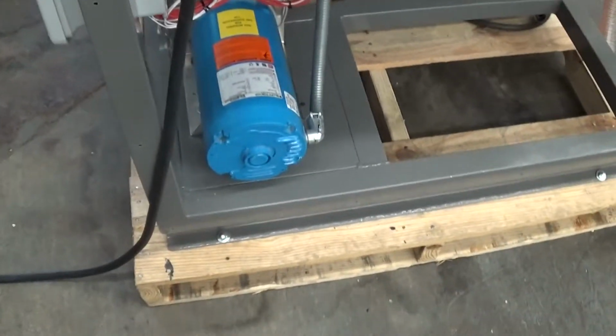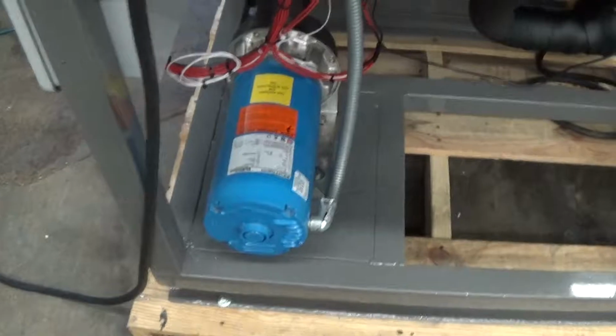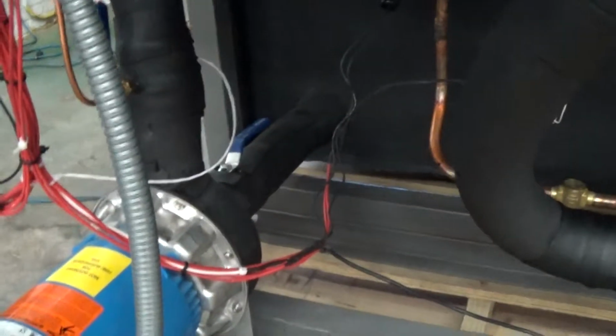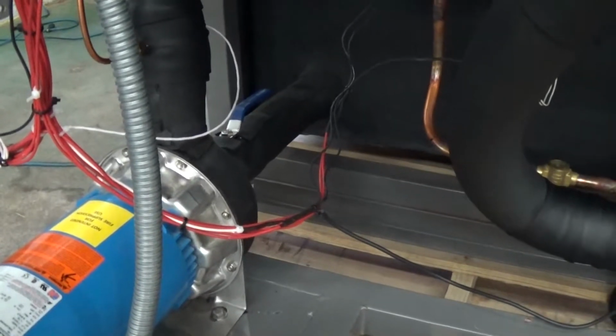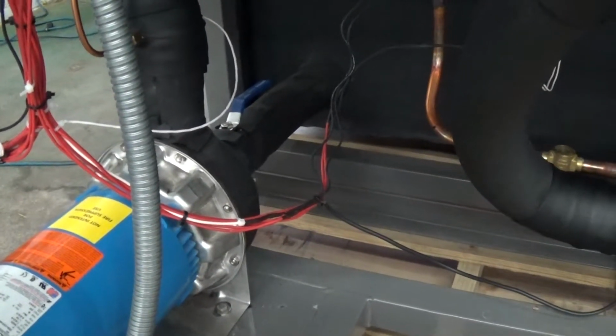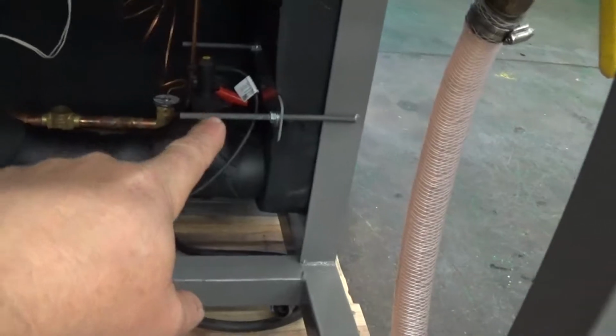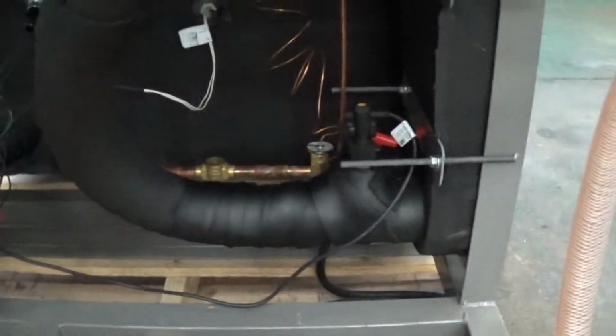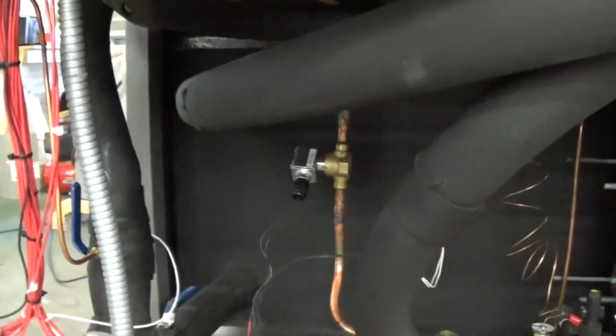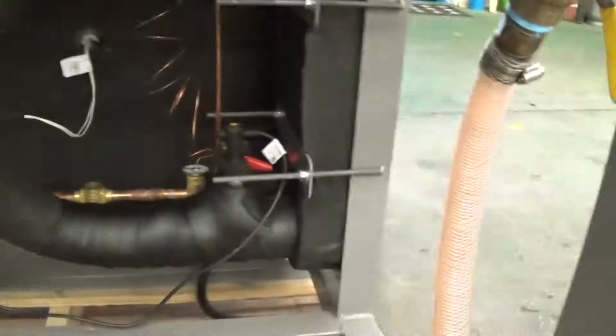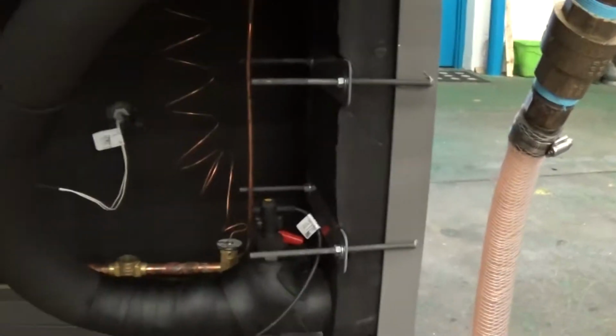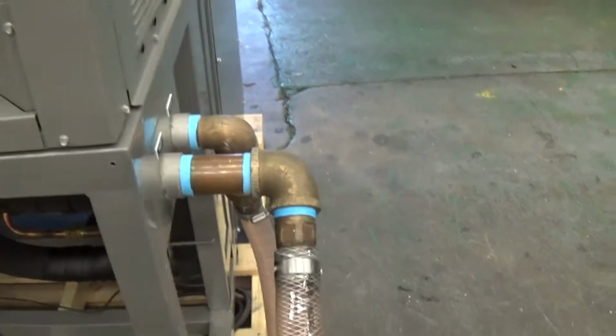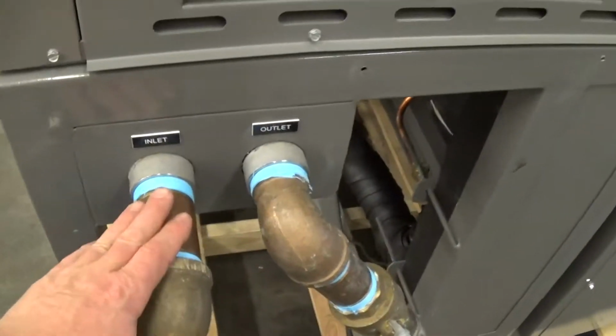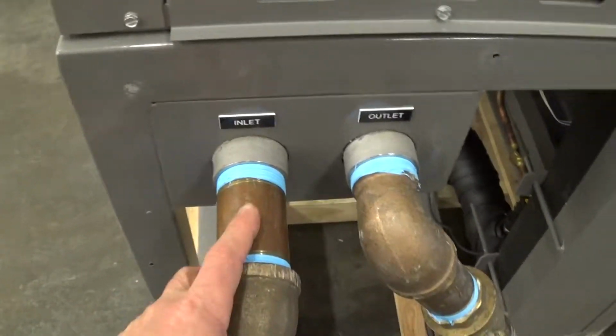This unit's outfitted with an upgraded 3 horsepower process pump, and the way this unit is piped is there's 2 ways you can pipe chillers like this. In this case here we've piped it so we're drawing from the tank, then out into the heat exchanger, then out to the process, and then it returns freely here back into the tank. What this affords us is that any pressure requirements of that brazed plate heat exchanger are first met. Then you can go out to your process and you can actually return back to the unit effectively at zero pressure.